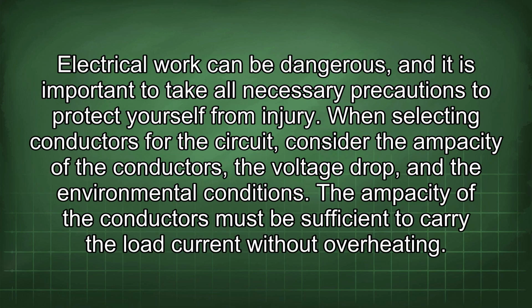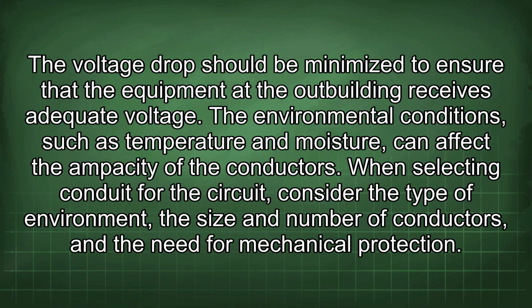Electrical work can be dangerous, and it is important to take all necessary precautions to protect yourself from injury. When selecting conductors for the circuit, consider the ampacity of the conductors, the voltage drop, and the environmental conditions. The ampacity of the conductors must be sufficient to carry the load current without overheating. The voltage drop should be minimized to ensure that the equipment at the outbuilding receives adequate voltage. The environmental conditions, such as temperature and moisture, can affect the ampacity of the conductors.